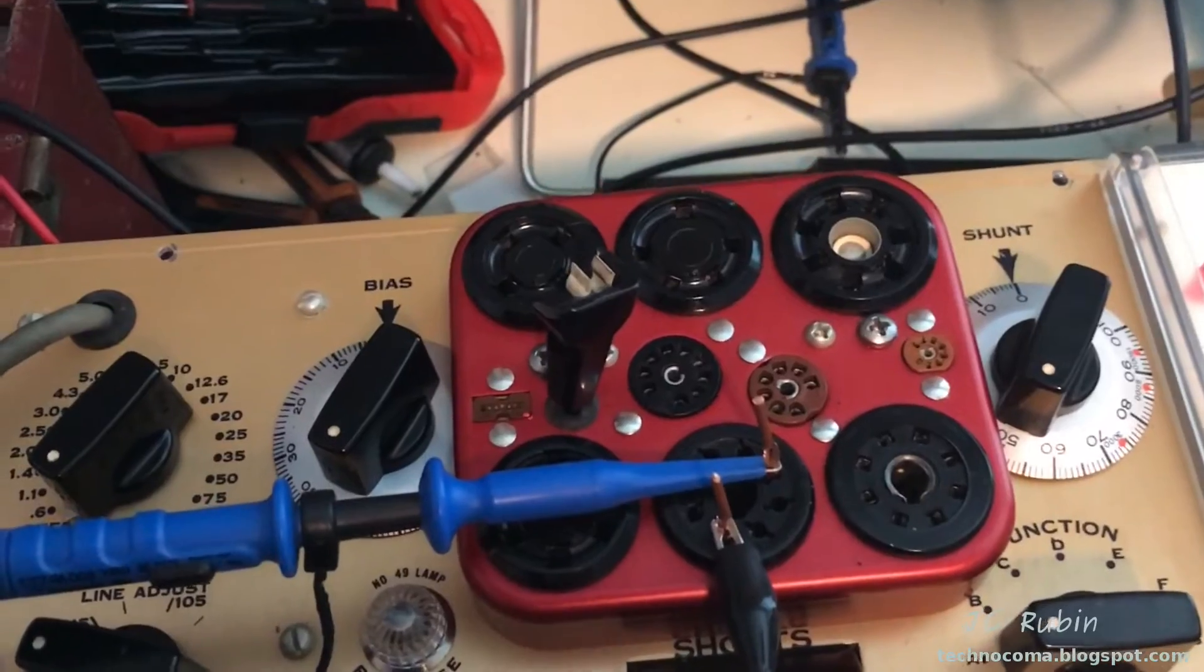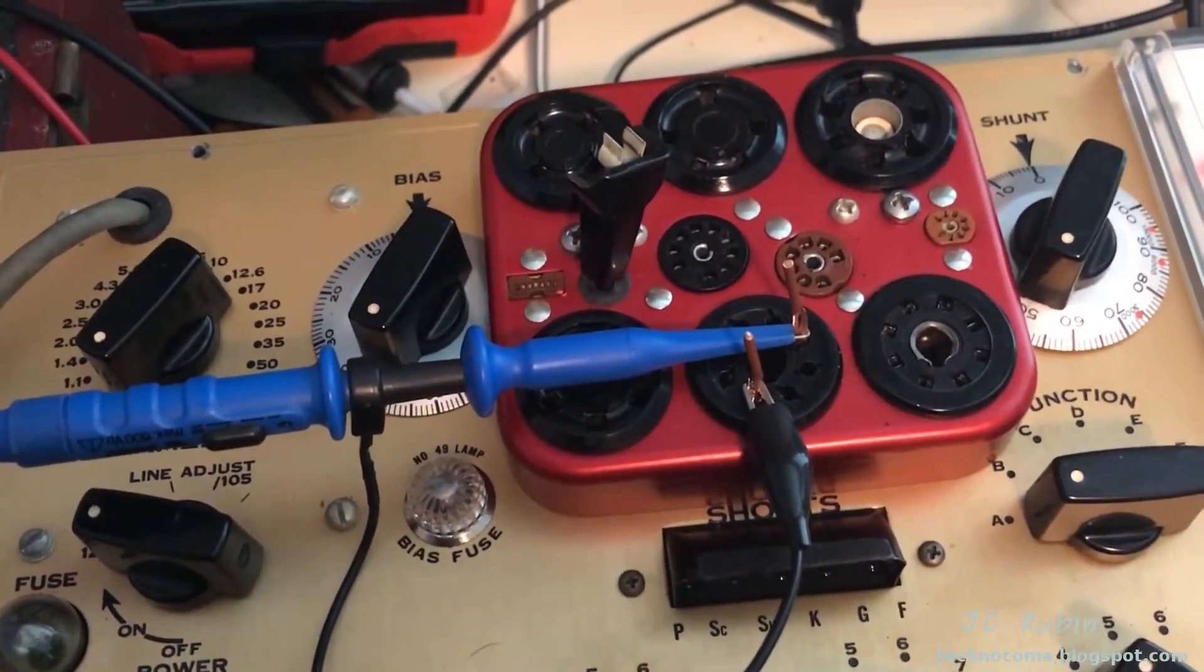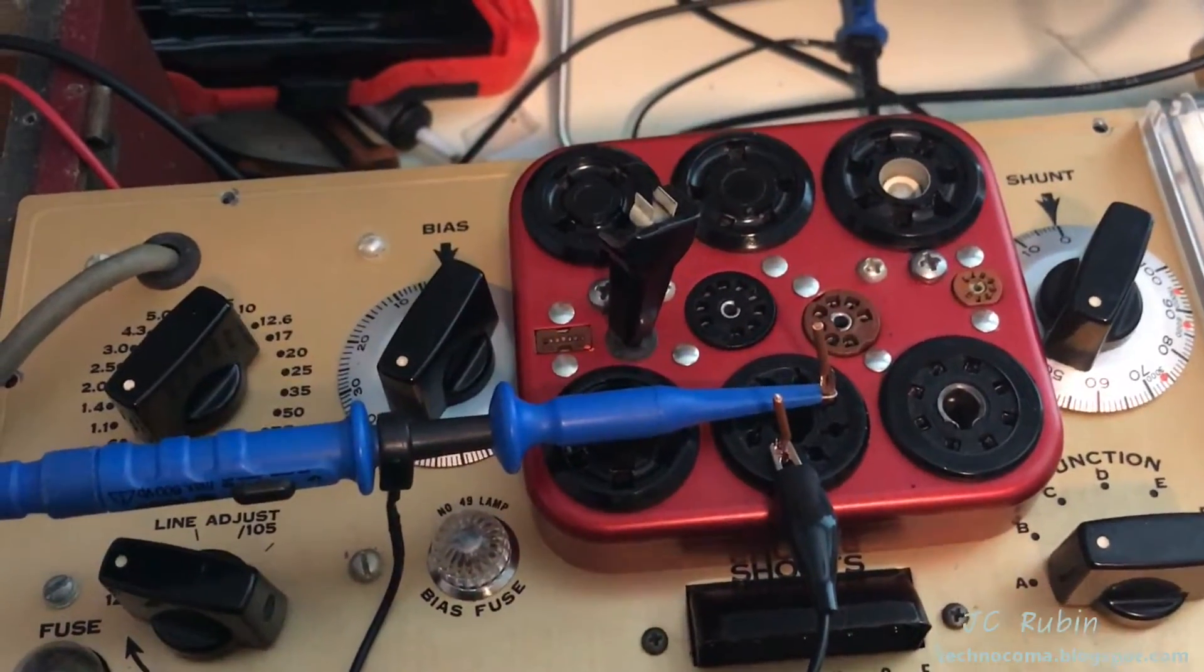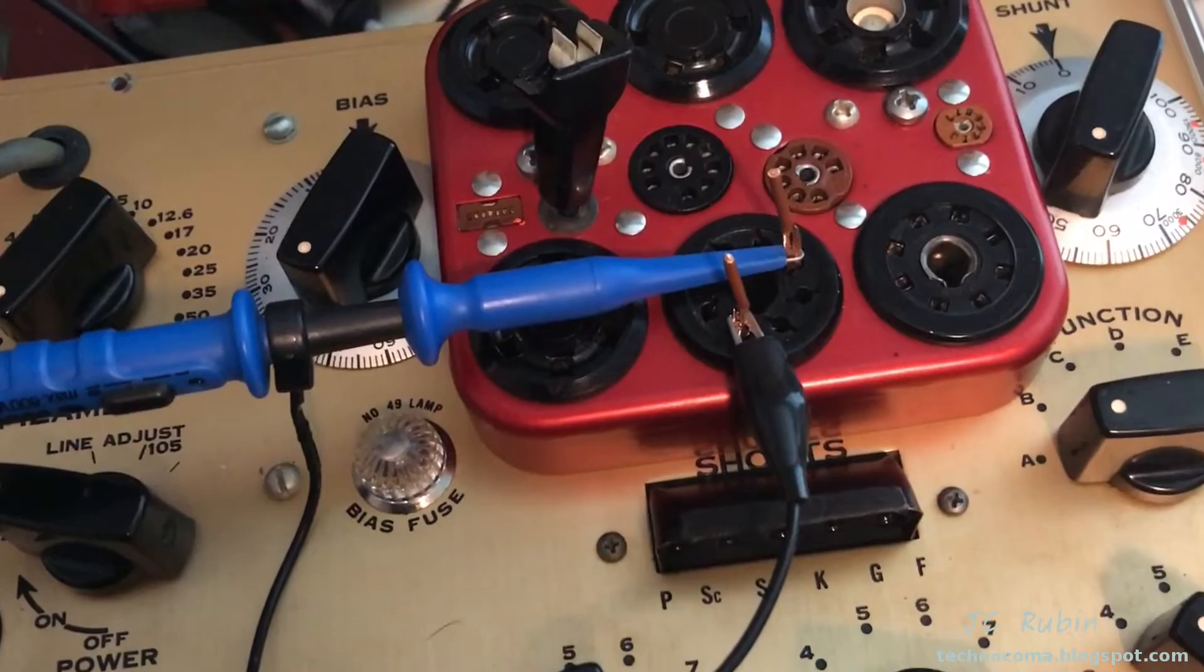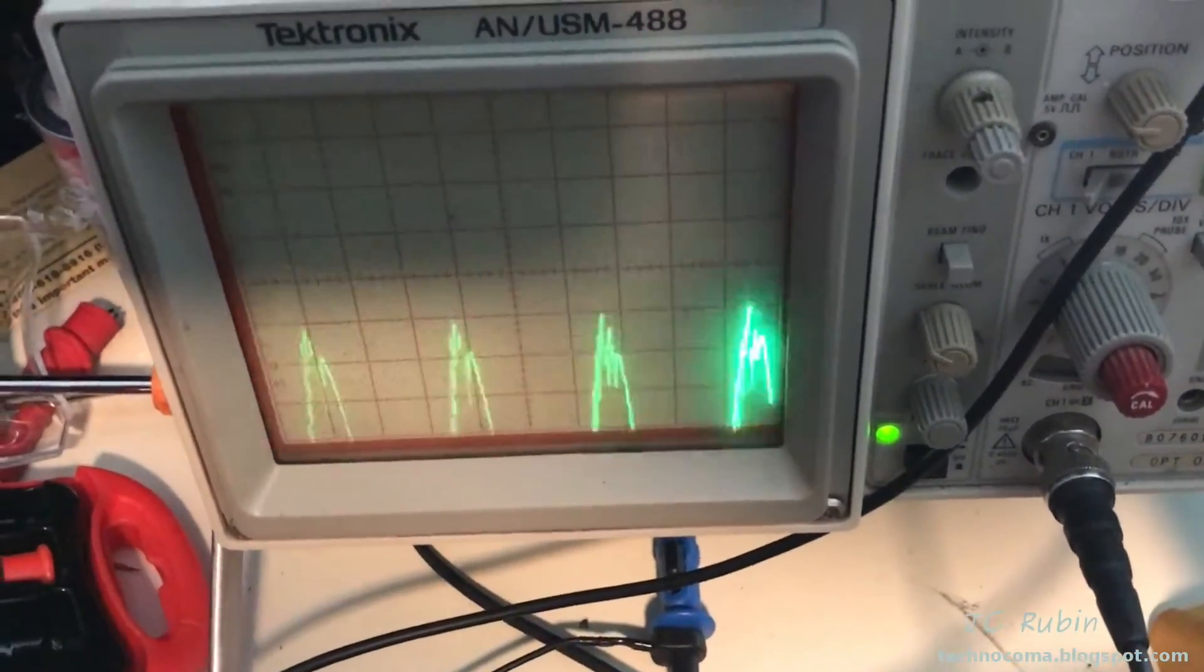This next step is part of the plate supply test. It's not explicitly mentioned in any manual, but it was on the website and seemed like a good idea. It was explained very nicely, so I decided to do it. I've got my oscilloscope here on pins three and eight. When I press the test button, I'm going to see the output of that rectifier, and I'm looking for an even pattern.